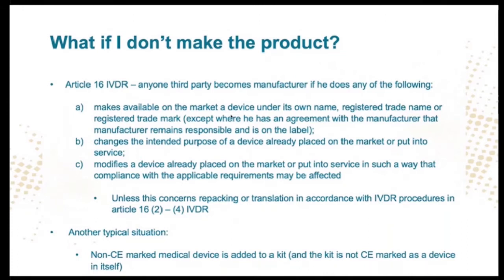Another one, and this was a ground that already existed under the IVD directive, but which was less clearly explained, if you change the intended purpose of a device already placed on the market or put into service. So let's say, for example, you have a COVID-19 test that is indicated for testing a specific mutation of the virus, but you are changing the intended purpose by marketing it also for, let's say, now the British and the South African and perhaps the Brazilian variant of the virus. That is changing the intended purpose. In that case, you become a manufacturer of the device, even if it's been placed on the market already, meaning you are responsible for CE marking the device for the new intended purpose. And if you don't, then you are placing an incorrectly CE marked device on the market, which can be enforced against.